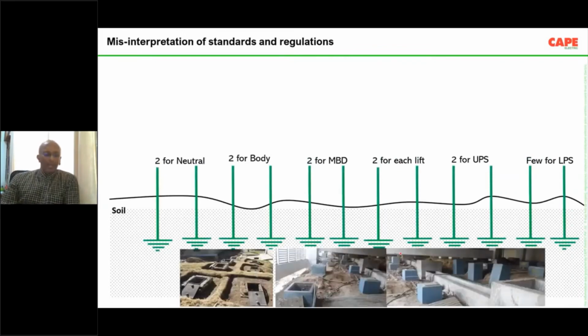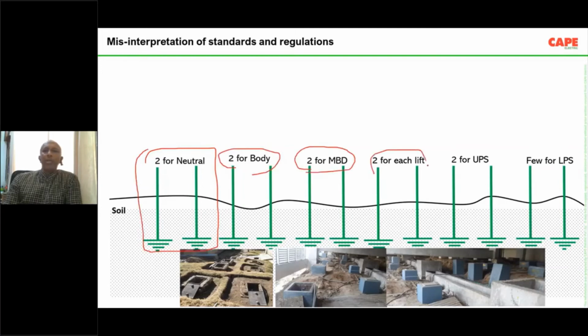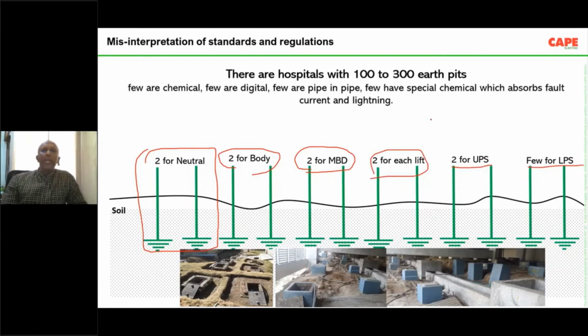Now, when we look at the concept of an earthed system, whenever we hear the word earthing, people immediately think that earthing means you take a wire and connect your system to an earth pit in soil. As a result of this concept, for the transformer neutral we have two connections to earth pits. For the transformer body, we have two more, then two for the main distribution board, two for each lift, two for UPS, two for the lightning protection system, and two for maybe medical equipment. And there are hospitals with 100 to 300 earth pits all around the hospital. Some earthings are chemical earthing, few are digital earthing, few are pipe-in-pipe earthing, few have some special things. I don't want to go into the detail of those things.